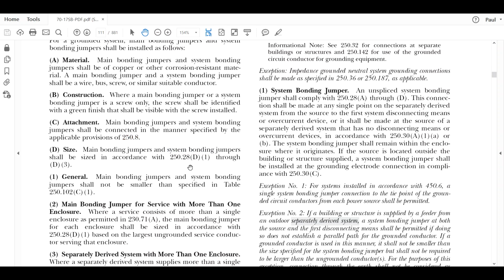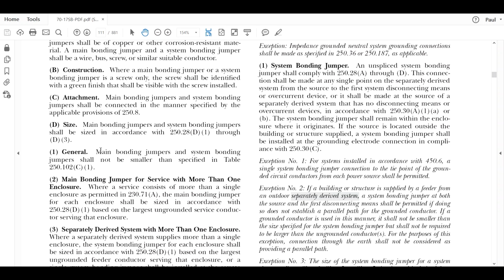The system bonding jumper is sized in accordance with 250.28(D)(1) through (D)(3). Well, (D)(1) is basically the one we're going to deal with because we only have one enclosure that we're supplying from this transformer application. It says main bonding jumpers, in our case system bonding jumpers, shall not be smaller than specified in Table 250.102(C)(1). Well, we've already done that, and we know that it can't be smaller than that. It's all based on the size of the derived conductors. We know that. So we're going to go back and look at the diagram.